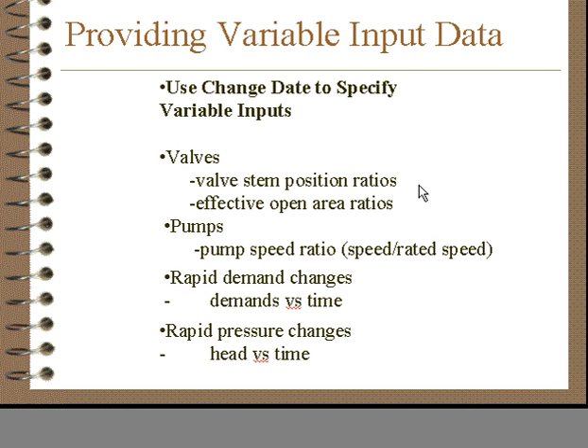For valves, the ratio is either the valve stem position ratio for standard valves, which means that when the valve is 50% closed, the stem has moved 50% of its total movement, or an effective area ratio which is used for non-standard valves, the customized valves. These ratios are the ratio of the effective area over the fully open area, so at 50% would mean that 50% of the effective area is available.